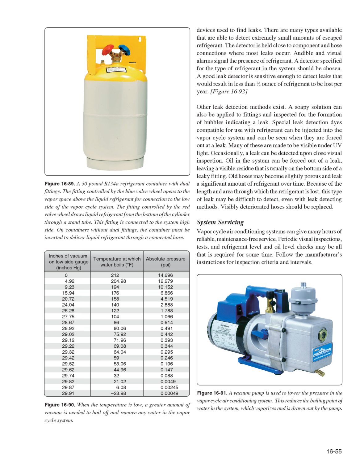Devices used to find leaks. There are many types available that are able to detect extremely small amounts of escaped refrigerant. The detector is held close to component and hose connections where most leaks occur. Audible and visual alarms signal the presence of refrigerant. A detector specified for the type of refrigerant in the system should be chosen. A good leak detector is sensitive enough to detect leaks that would result in less than 1/2 ounce of refrigerant to be lost per year.